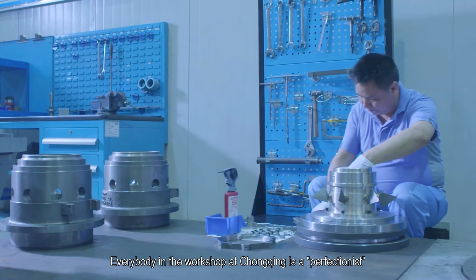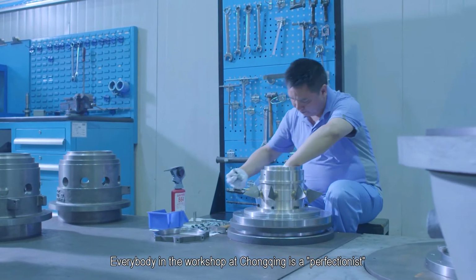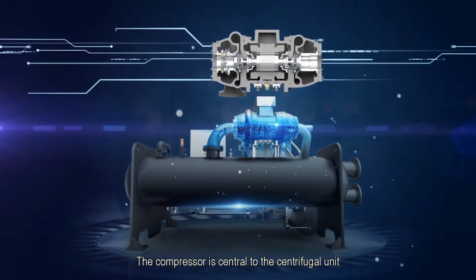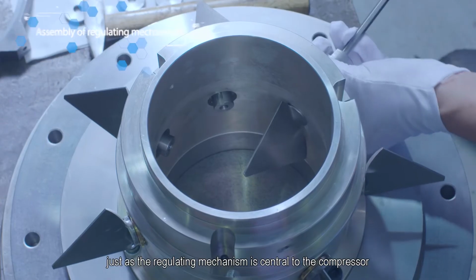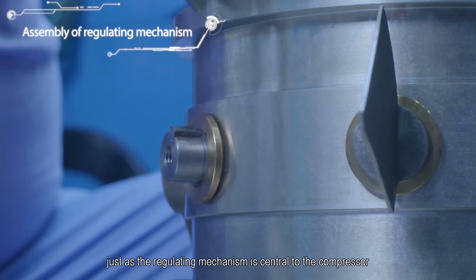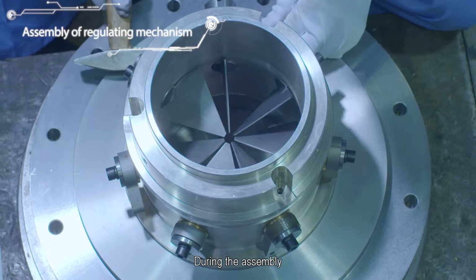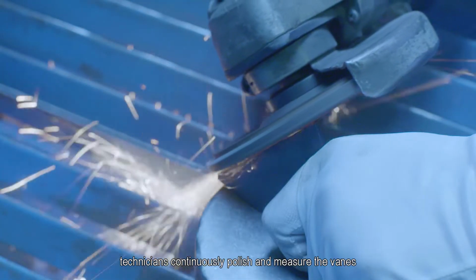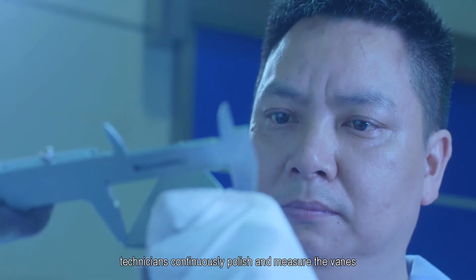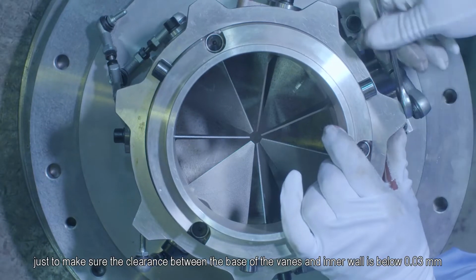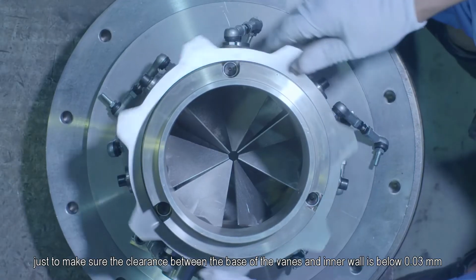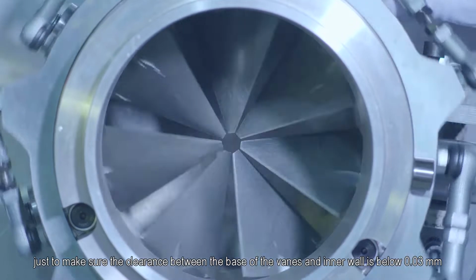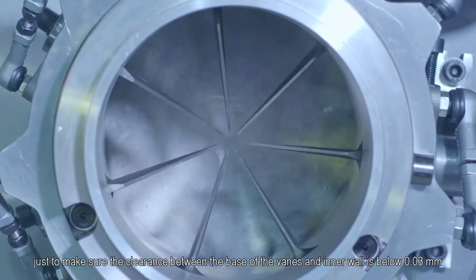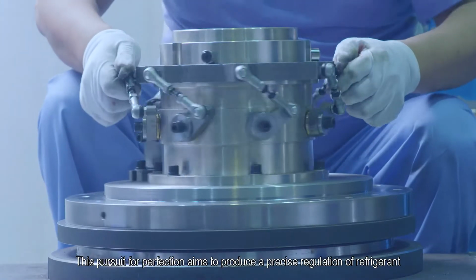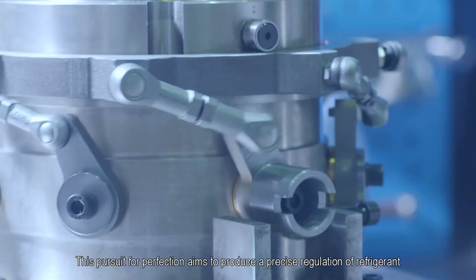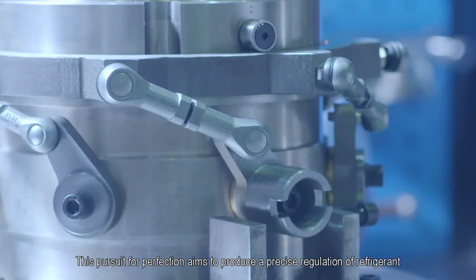Everybody in the workshop at Chongqing is a perfectionist. The compressor is central to the centrifugal unit, just as the regulating mechanism is central to the compressor. During the assembly, technicians continuously polish and measure the vanes, just to make sure the clearance between the base of the vanes and the inner wall is below 0.03 millimeters. This pursuit for perfection aims to produce a precise regulation of refrigerant.